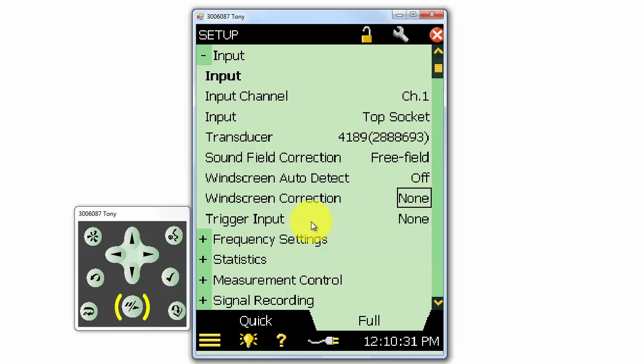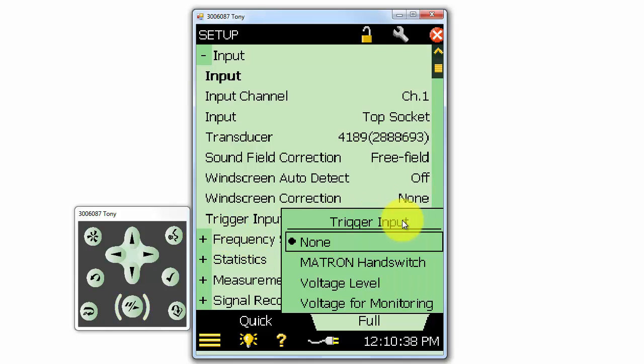Under trigger input, we can select what is connected to the trigger input connector. The Matron hand switch and voltage level can be used to control the start and stop of signal recording. When we select voltage level, anything over a 2 volt input will start the signal recorder, and when it drops below 1 volt, the recording will stop. The voltage for monitoring setting is for monitoring the voltage at the trigger input, which can be used together with the notifications from the preferences menu.